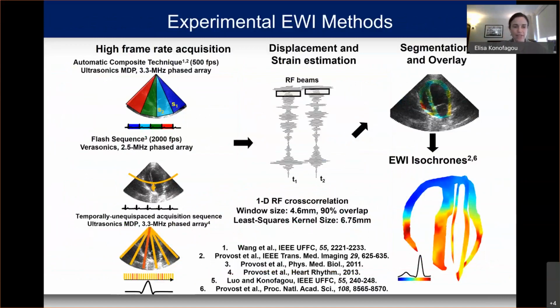We've also developed what we call the composite technique, which uses ECG gating. You narrow down the field of view and borrow from four different consecutive cardiac cycles to compose a new image. This has the advantage of preserving higher spatial resolution, but the disadvantage, especially with arrhythmias—paroxysmal arrhythmias, meaning not stable but more transient—is that it won't be the most efficient method when arrhythmias are changing.